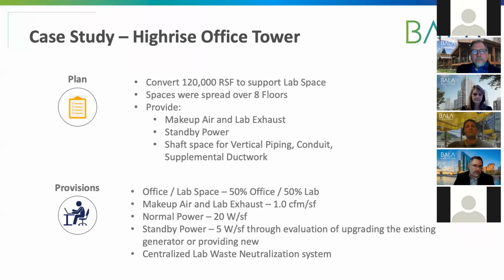With this building, we ended up targeting 120,000 square feet for conversion, working our way back from our evaluation phase. Essentially, when evaluating the building, as Chuck mentioned earlier, we're looking for our lowest common denominator across the different utilities. The electricity was fine, and we found the plumbing was fine. Our short straw turned out to be the physical space on the roof where we could fit the exhaust.